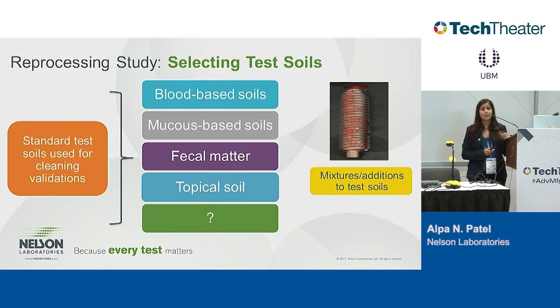I remember we had one validation we had to do for a liposuction, and it was a canister that was reused, and we had to come up with a soil to simulate the fat in the canister. What we did is we took blood, added Crisco to it, blended it together, and it was exactly the consistency of the fat that would be removed during the procedure. And then we added it to the canister and tested it that way. So there are options that are open to mimic exactly what your device or your product would see during contamination.